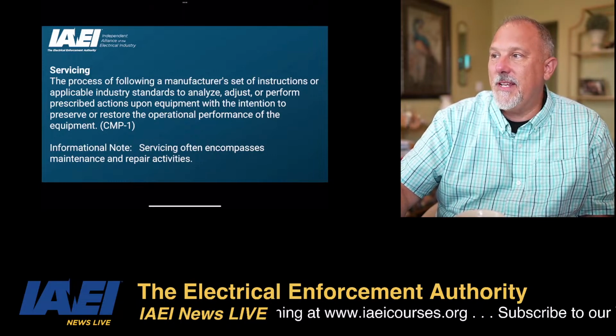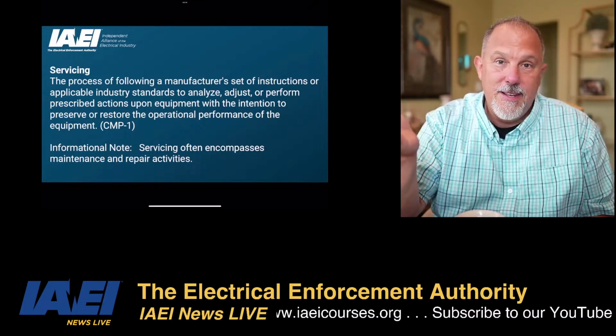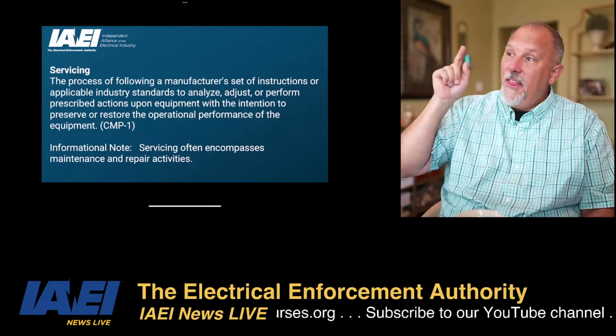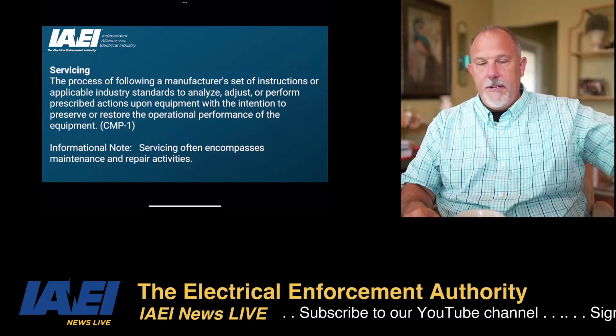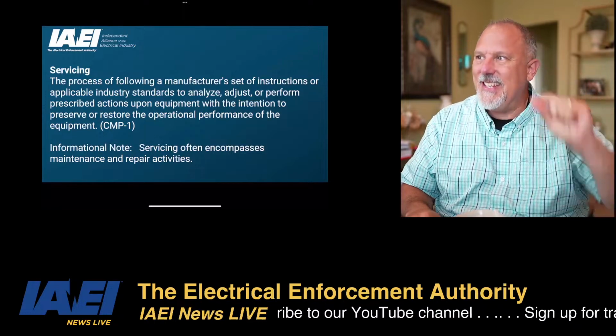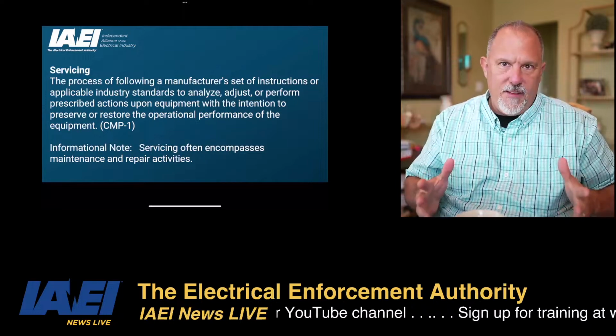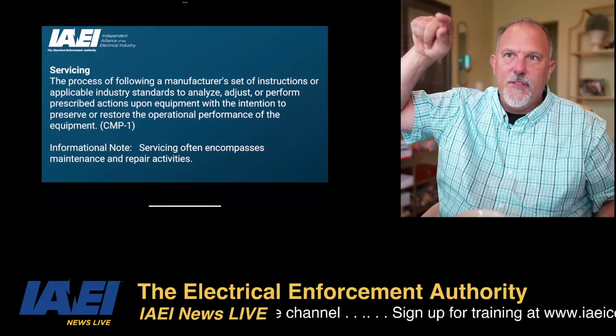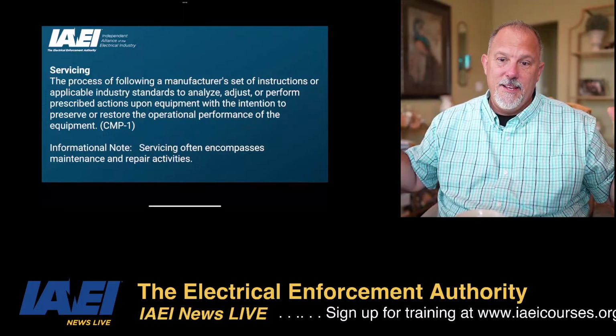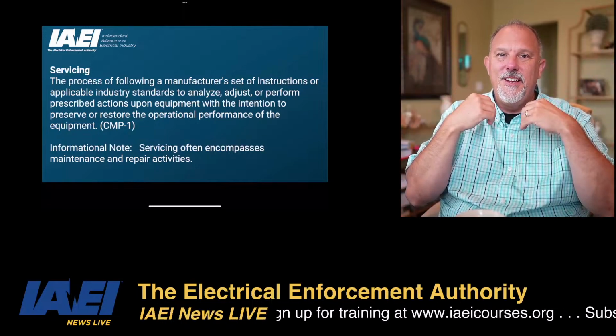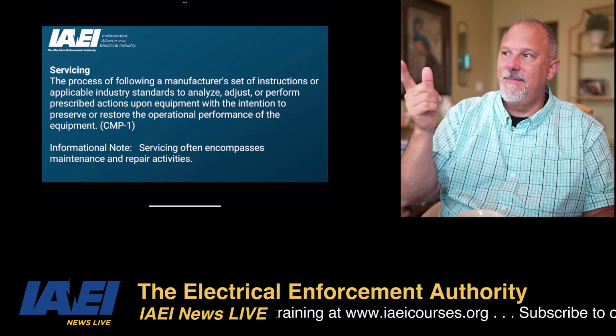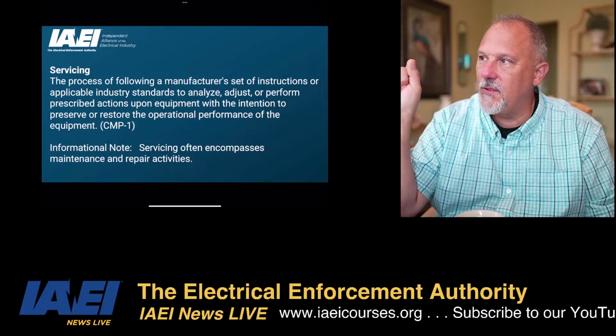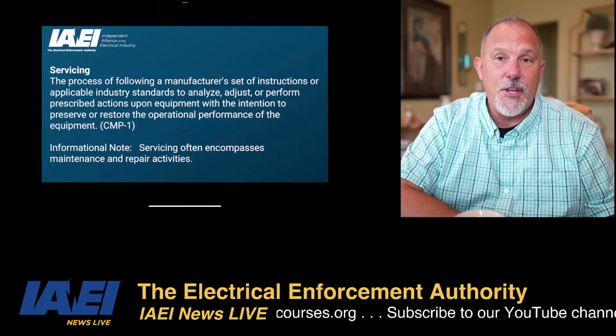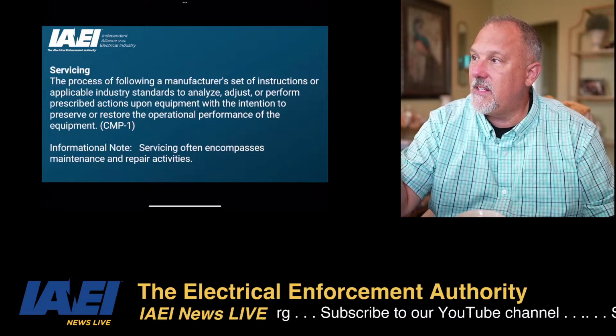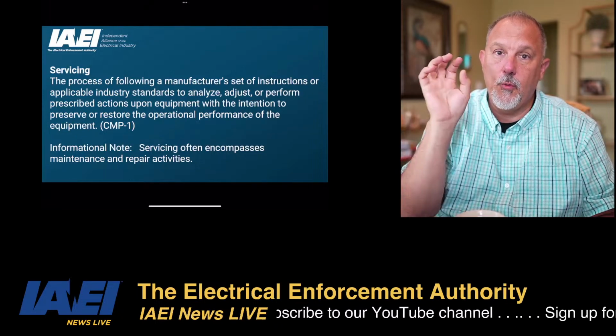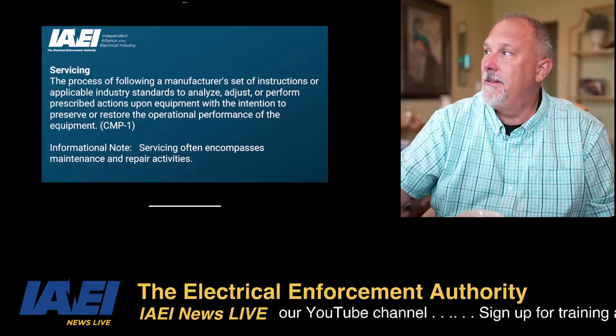700.3 says reconditioned transfer switches shall not be installed. So Daryl, here's a problem. In my opinion, with that language in 700.3, even if you took an existing transfer switch and said, this relay failed, that bus bar, the screws came out, or whatever, and you didn't remove it from installation and just reconditioned it in place, you're not violating that section of the code anymore. If it said not be permitted, you would be violating it if you reconditioned it in place. That's my heartburn with that language.